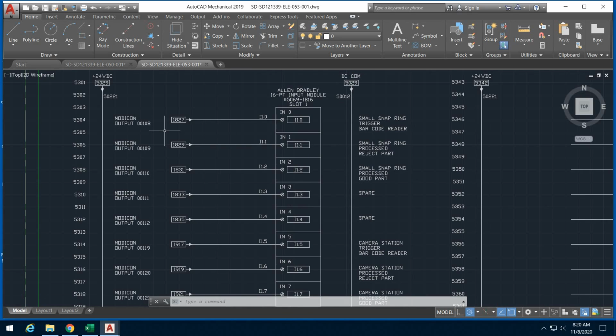Now, if you had like a switch, like a 3-wire prox, technically we're supposed to draw the 3-wire prox or the limit switch, and then put a wire all the way to ground, for the blue wire. On the drawing, we do not do that because it gets messy crossing the input card with all those wires. However, it's inherent, and it has to be there for the switch to work.